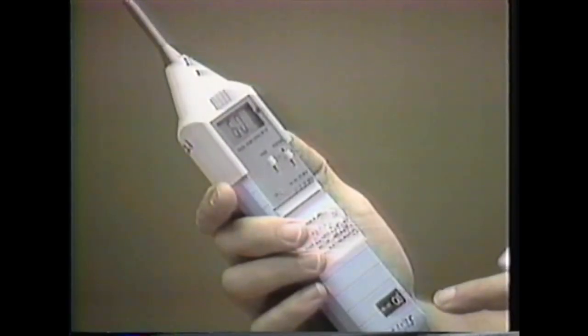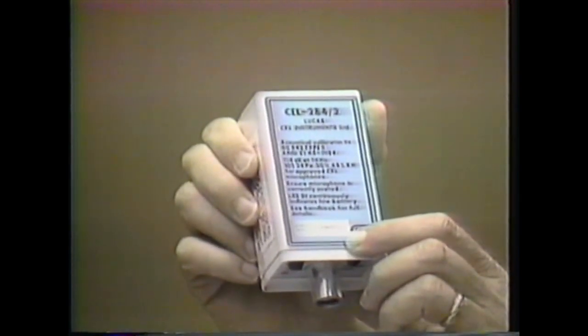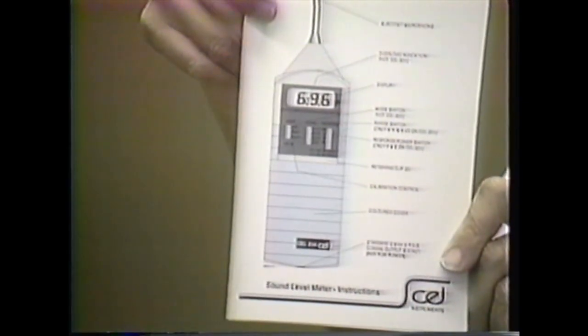After we've completed the calibration, a critical element here is the documentation. Can't emphasize that aspect enough. So we record the manufacturer, recommend you record the model number, and also it's essential that you put down the serial number of the instrument that you are planning to use or will be using. In addition, identify the calibrator that you're using and document its serial number as well on the appropriate form for the type of survey that you're doing. Keeping in mind that whether it's this instrument or others, always refer to the manufacturer's literature for the particular instrument in question.